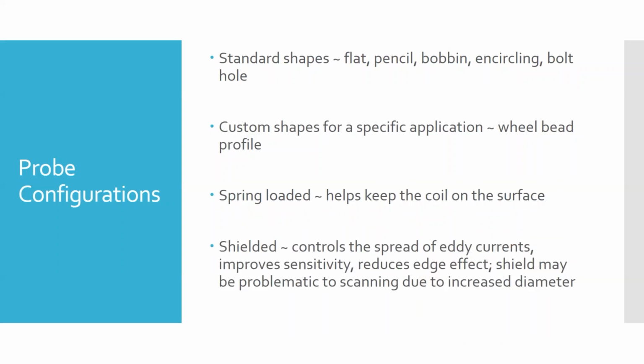There are some other standard shapes that work for different object or material shapes, like pencil probes, bobbin probes, and the like, designed for general purpose on certain styles or shapes of objects. There are also custom shaped probes for specific applications, like wheel bead seat profiles. Another one is probes made to fit into the fir tree areas on fan blades, compressor blades, or turbine blades - those high stress V-shaped areas with a lot of stress risers that could be prone to cracking.